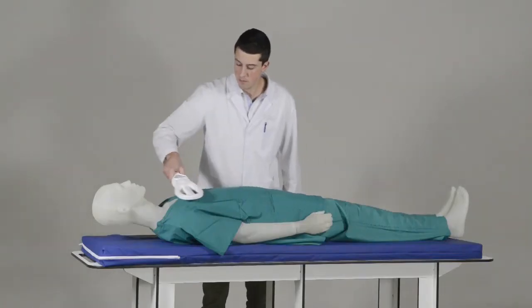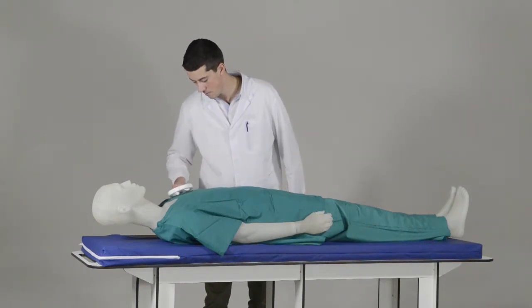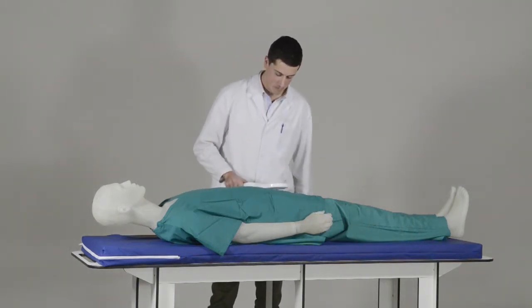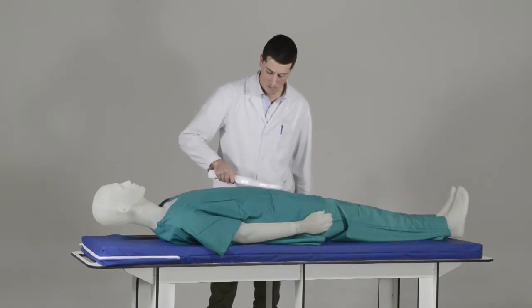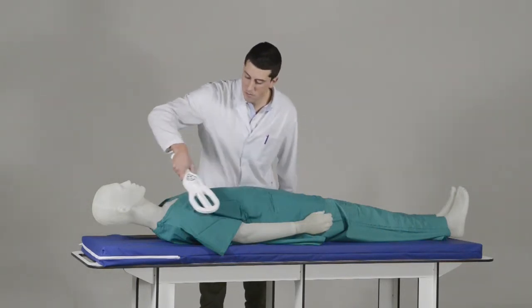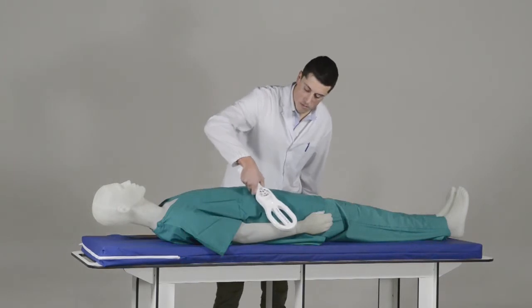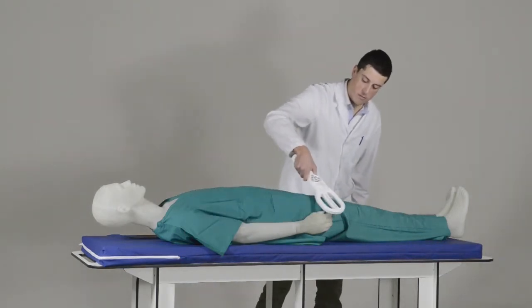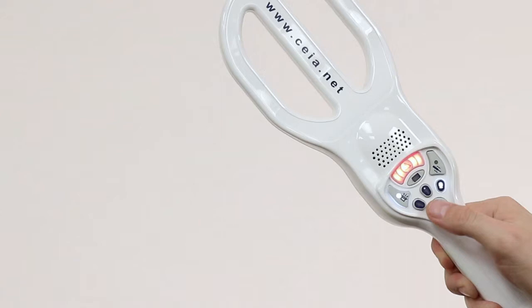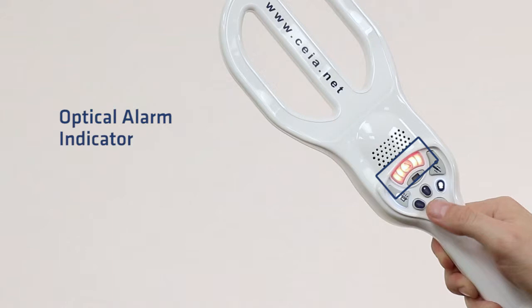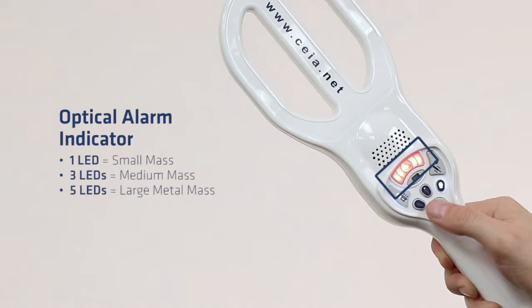Scan the patient by sweeping the detector across the area to be inspected. Keep the movement of the device slow and controlled while maintaining a distance of approximately ½ inch from the surface of the patient. Moving the device too quickly or with erratic movements may trigger a false detection. When a metal mass is detected, in addition to the current selection of audio and/or vibration alarm indicators, the optical alarm indicator will provide a red signal proportional to the size or distance of the object. One LED indicates a small mass, 3 LEDs indicates a medium mass, and 5 LEDs indicates a large metal mass.